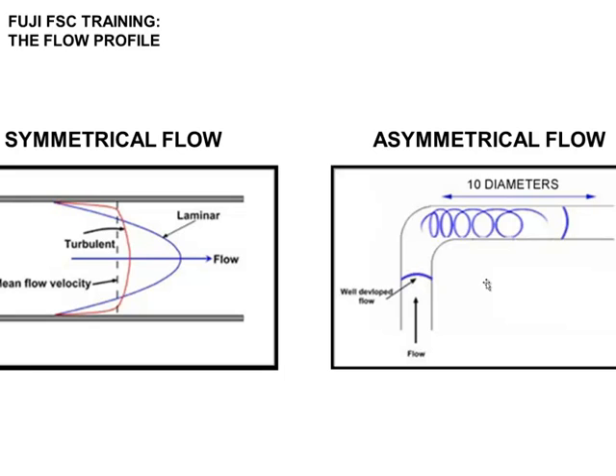Ultrasonic transit time flow meters need straight run of pipe for optimum flow performance. Every meter has a certain set of parameters, and I think you'll find the straight run of pipe parameters pretty much industry standard. So what you want is what's called a symmetrical flow profile. I need my elbow here. I need 10 pipe diameters to here and another 5 pipe diameters here before the next elbow. So that's what we call a symmetrical flow profile.